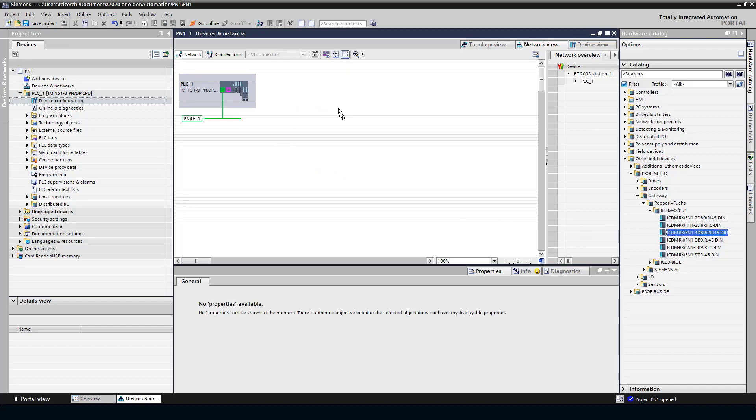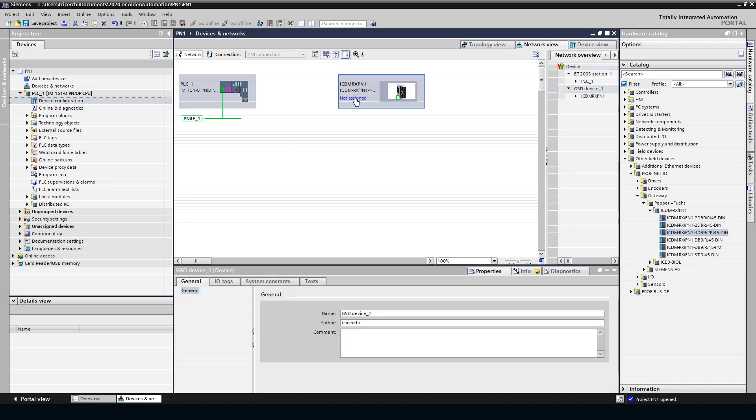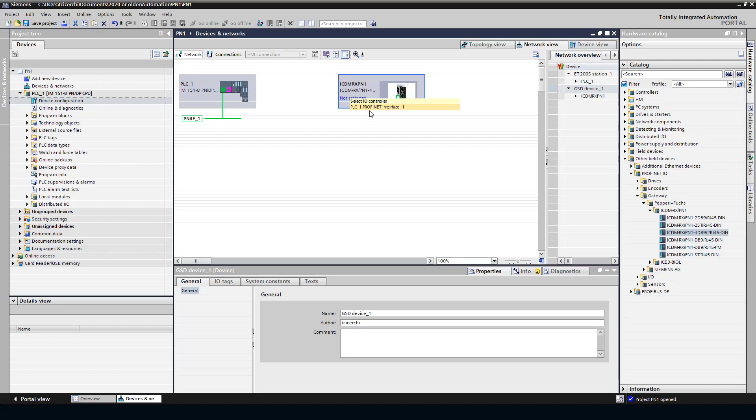And now, once it's in the system, I can drill down on the PROFINET and find my ICDM-RX-PN1 and I'm using the four-port model here. I'll drag it over. Once you've dragged it over, where it says not assigned, you can just check, select the PROFINET device. And it will draw the line for us. Good to go.